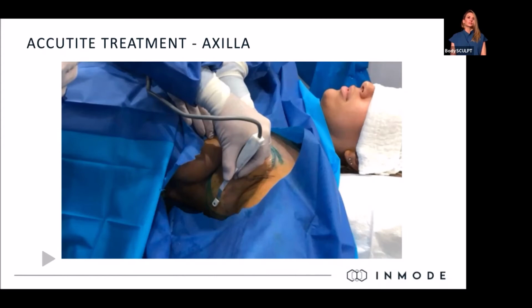Remember, kilojoules is just a measurement of work. And you actually want to work the tissue over an amount of time, because that's how it works, no pun intended. You don't want to be frustrated or have the doc get frustrated when the thing keeps shutting off. So one troubleshooting tip I've had is that sometimes if there's not enough tumescent in that area, especially with this smaller handpiece, the Accutite, you'll continuously get temperature surges. It probably means either A, they're outside of their area of tumescent, or B, they didn't use enough tumescent. So if you're constantly getting that temperature surge, either reposition them deeper, or encourage them to add tumescent. Those have been the two reasons why you get continuous temperature surges.